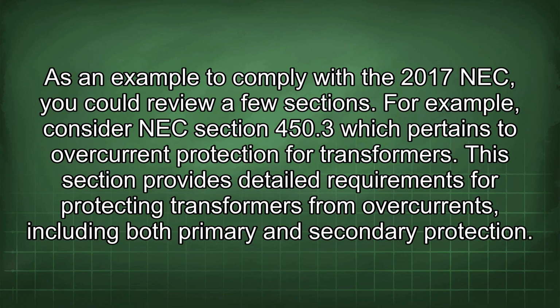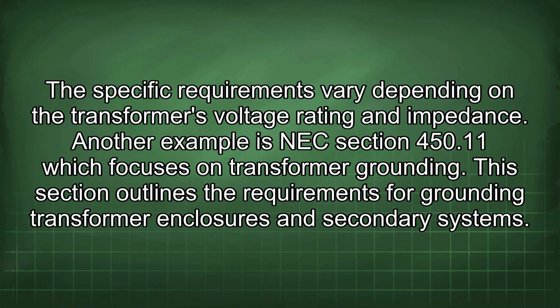As an example, to comply with the 2017 NEC, you could review a few sections. For example, consider NEC Section 450.3, which pertains to overcurrent protection for transformers. This section provides detailed requirements for protecting transformers from overcurrents, including both primary and secondary protection. The specific requirements vary depending on the transformer's voltage rating and impedance.